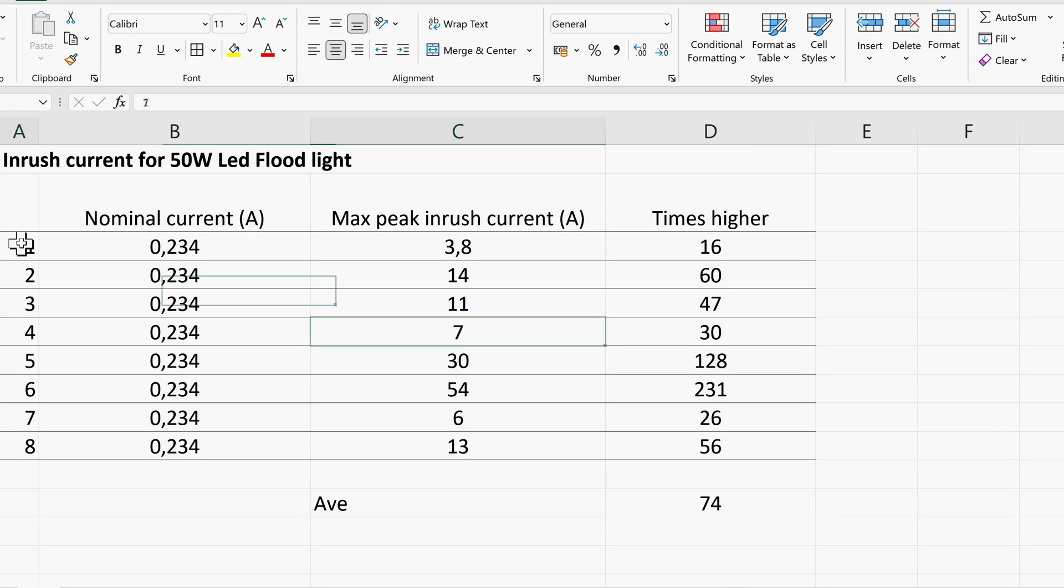Okay, just analyzing some of the results. All right, on the left hand side here I've got the attempts, when I was switching it on and off. And then these are the nominal currents. The current stays the same. So the current for the 50 watt floodlight was 0.234 amps. And over here in column C these are the peak inrush currents. What I have here in column D is the times higher. How many times higher was the maximum peak inrush current than the nominal current. So looking at the first attempt, 3.8 amps is 16 times higher than the nominal current. Over here you can see that 14 amps is 60 times higher.